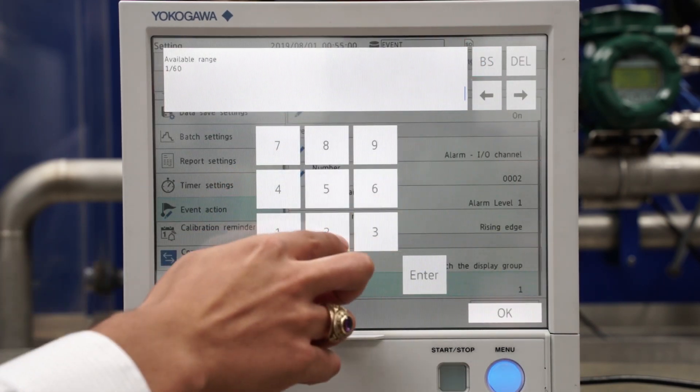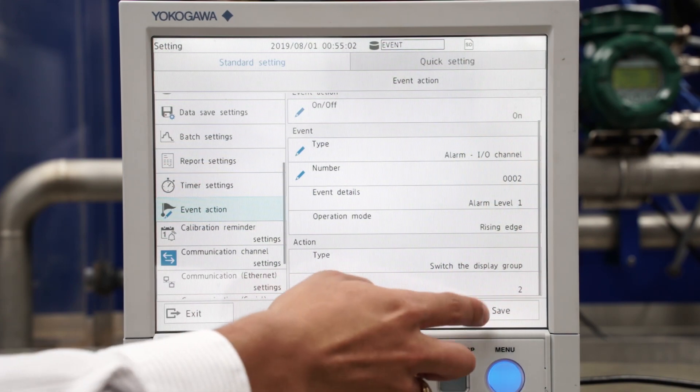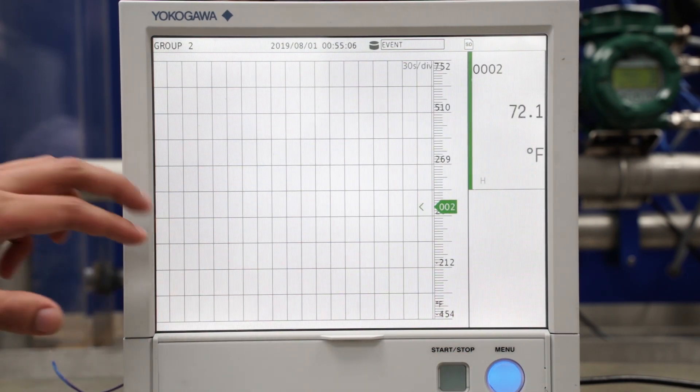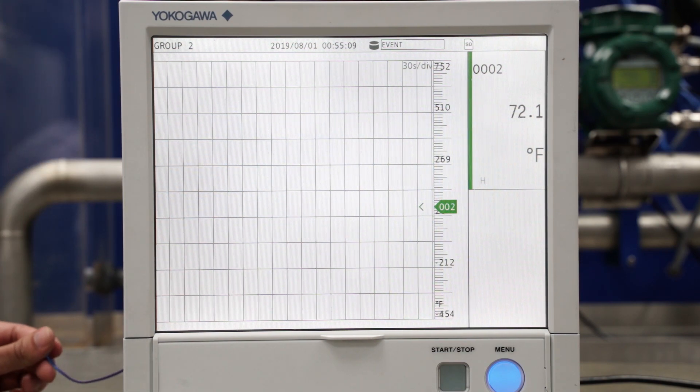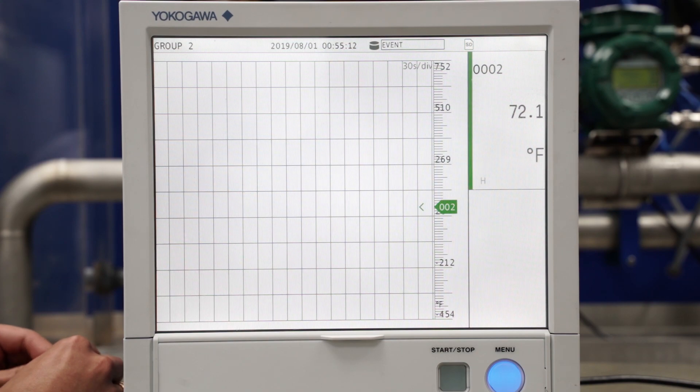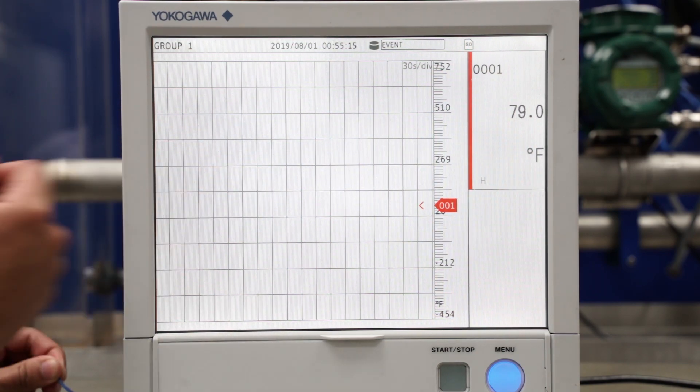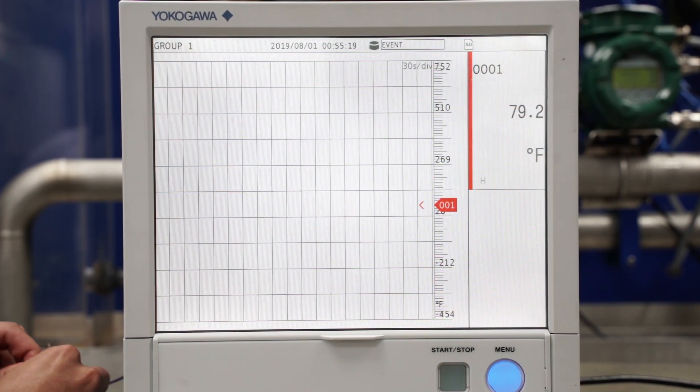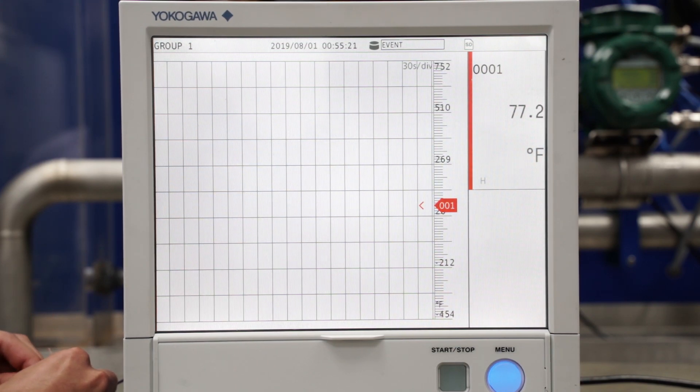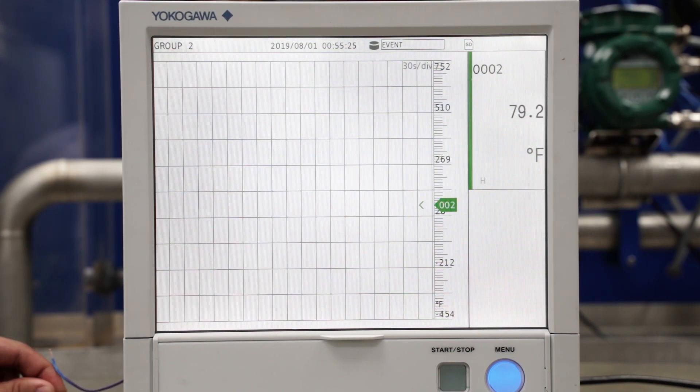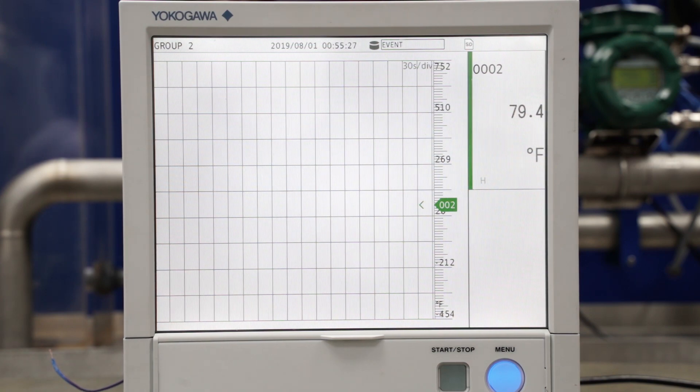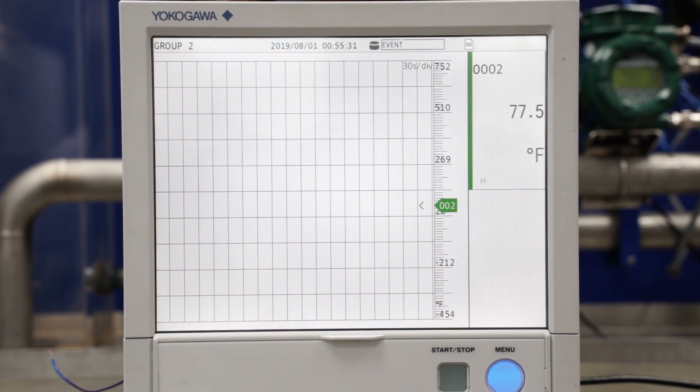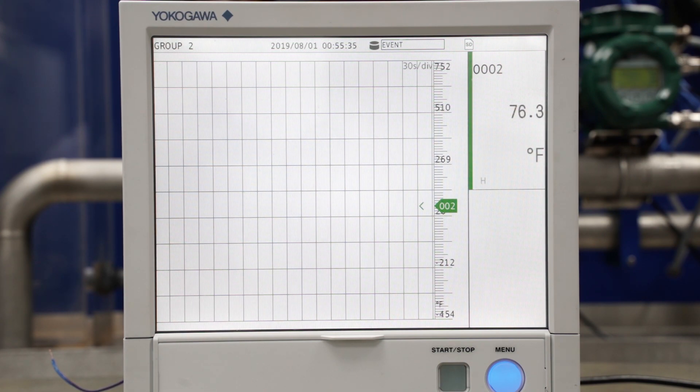And now this is display group two, and it should change to display group one when it's above 78. As you can see, it changed there. Now I'll switch it back to display group two by heating up the second thermocouple. As you can see, once it went above 78, it switched to display group two. That means my event action is working with the alarms, so that is it.